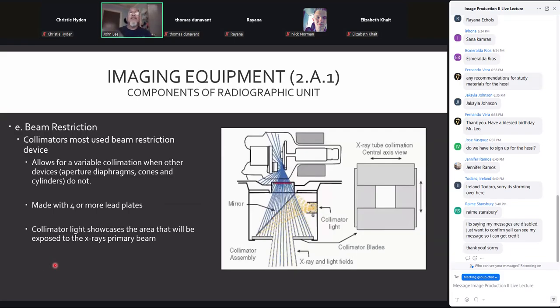Outside of the tube housing, we have our collimator housing. This will allow for manipulation of the light and radiation field. And remember, there should be a congruency between those two, meaning that the light field that we see on our image receptor and on our patient should be very, very close to the actual radiation field as well. Now, the only way that we can really get as close as we do is to put that collimator light the same distance from the mirror as our focal spot is from the mirror. If one of these distances is off, then the beam divergence will be off for one of those fields, and our light field radiation field congruency will be completely off. Okay.